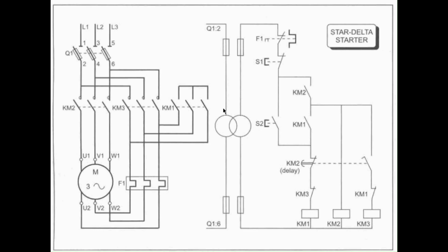This goes through a fuse. This is a transformer and another fuse. This now steps down to a lower voltage, which is safe to be connected to control and instrumentation devices. So let's walk through the system, starting the motor. First of all, important to note is that circuit diagrams are always shown with power off and everything in its open position.